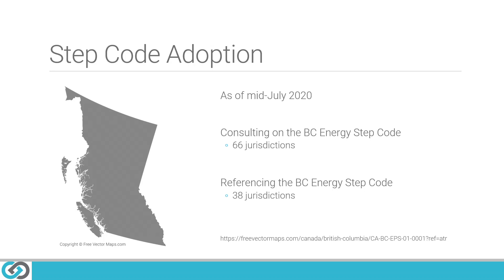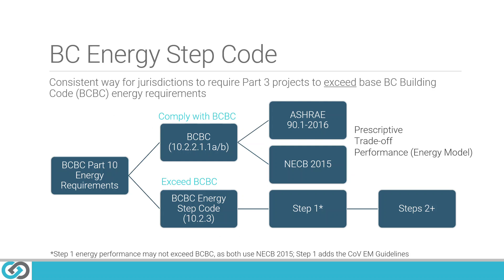As of mid-July 2020, there were 66 jurisdictions consulting on the BC Energy Step Code and 38 jurisdictions already referencing it. The Step Code was designed as a consistent way for jurisdictions to require Part 3 projects to exceed base BCBC energy requirements. There are currently two ways to comply with BCBC: using ASHRAE Standard 90.1-2016, or using the National Energy Code for Buildings, NECB 2015.